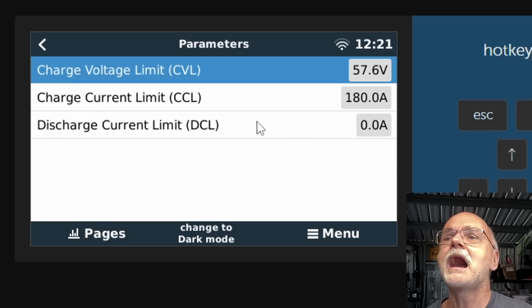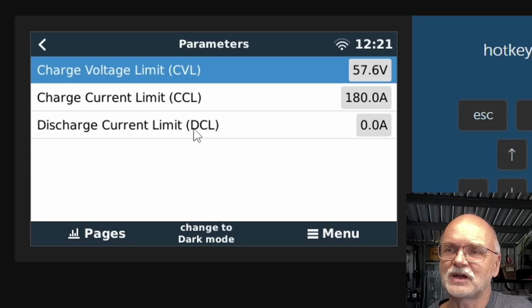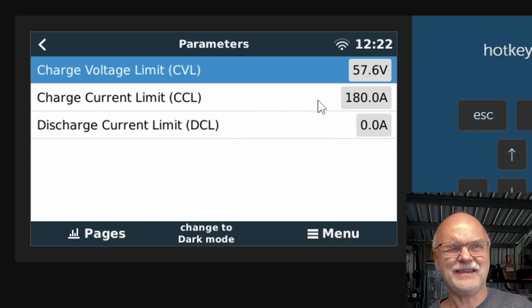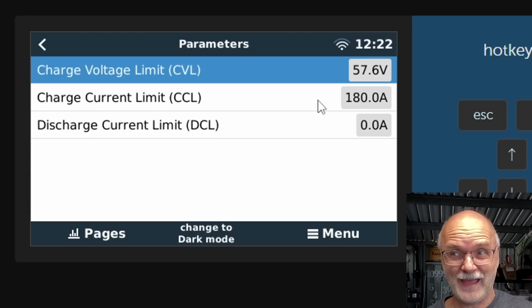Parameters, ah, here we go. The discharge current limit is on 0. The charge current limit is on 180. That is 100 plus 100, and then they take 10 amps away per battery maybe?